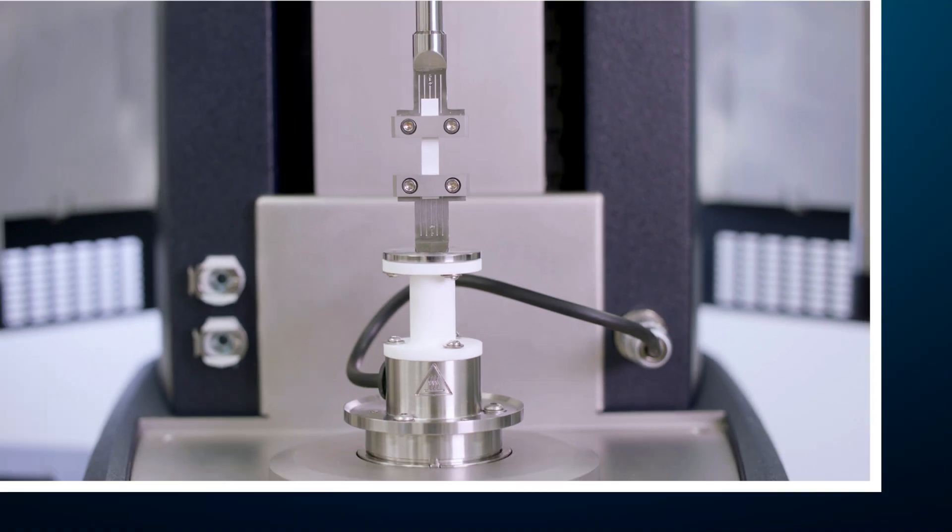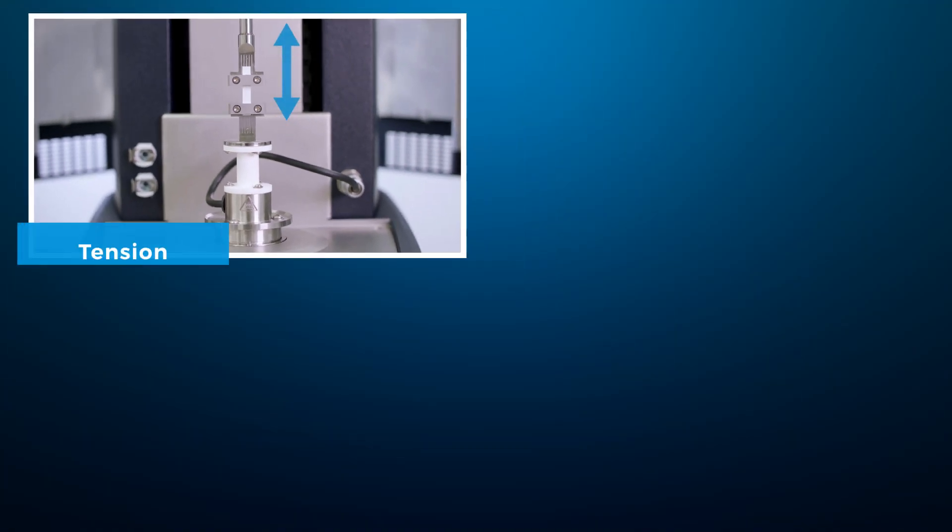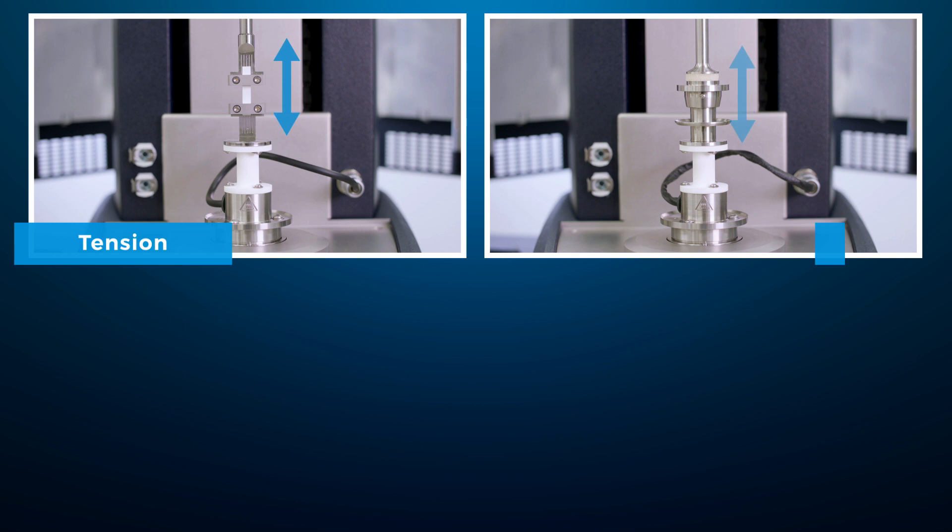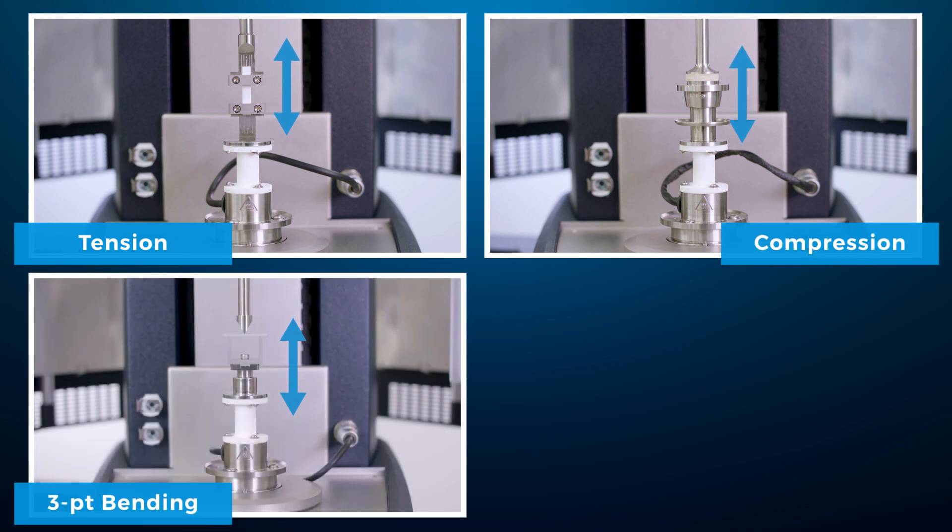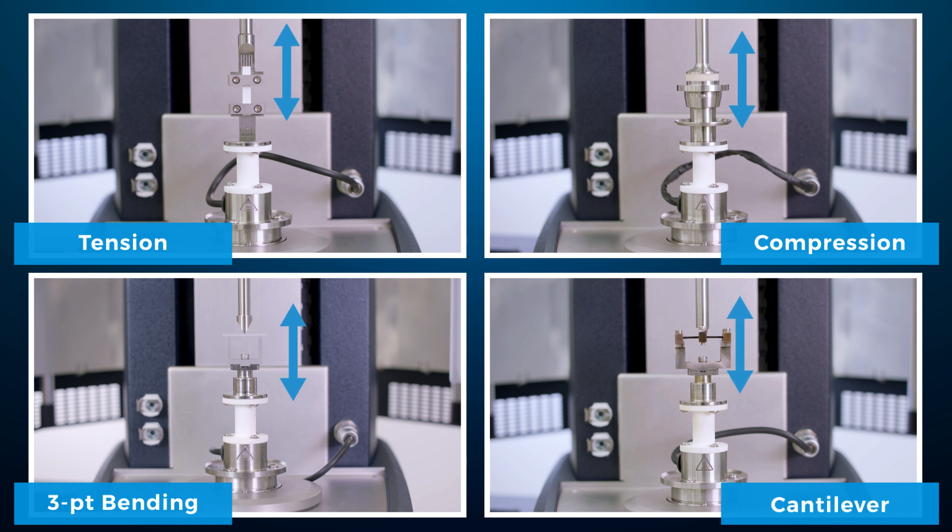In addition to standard torsional testing, the Discovery Hybrid Rheometer's integrated dynamic mechanical analysis capabilities also offers the ability to test samples under axial deformation mode. A full range of standard DMA geometries such as tension, compression, bending, and cantilever are available to perform DMA measurements on your rotational rheometer.